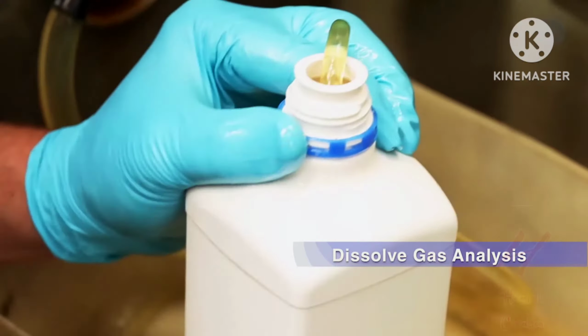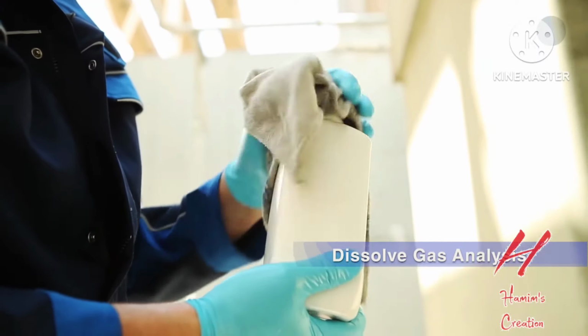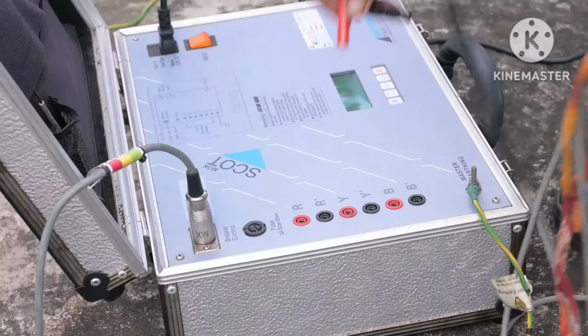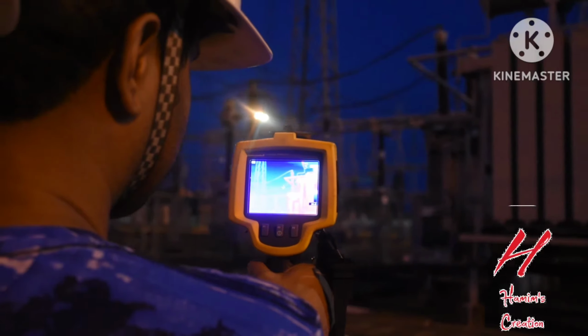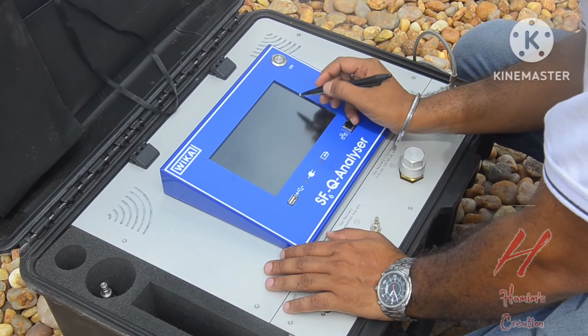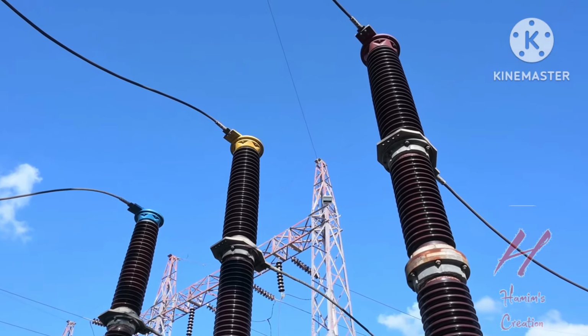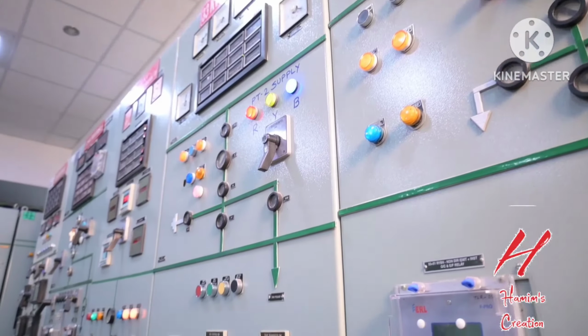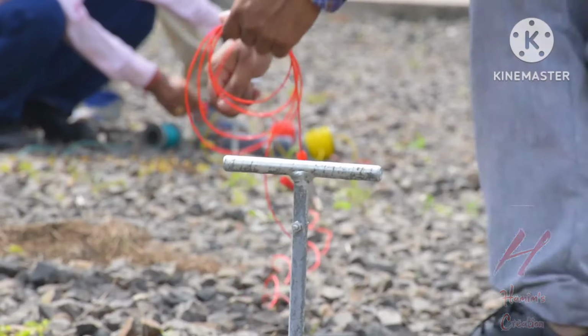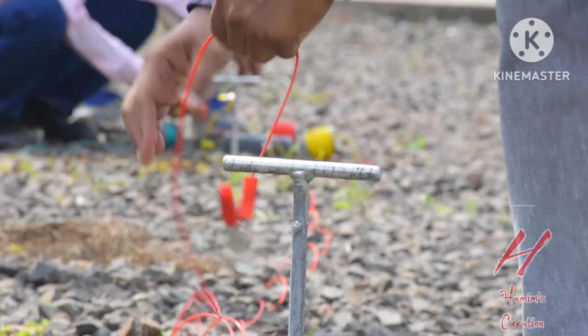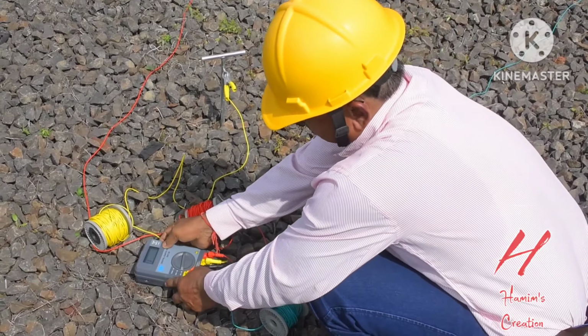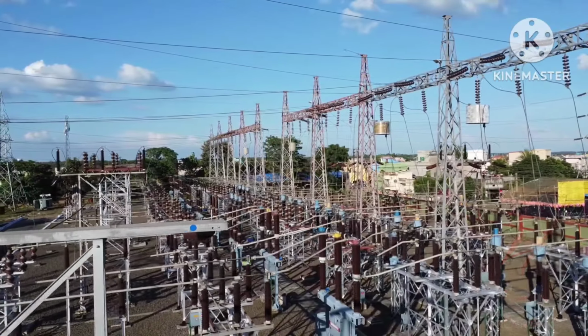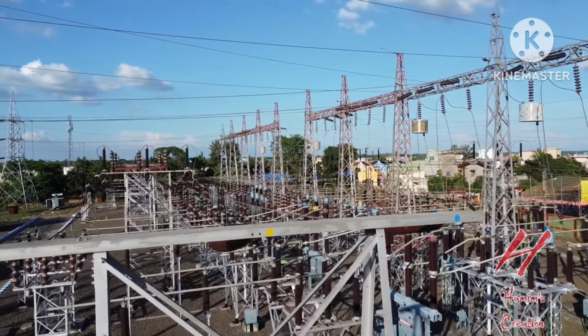dissolved gas analysis test of transformer oil, contact resistance measurement, breaker timer of circuit breaker, thermovision scanning of clamp connectors, dew point measurement of SF6 gas of circuit breaker and periodical testing of relays, earthing resistance test by Megger make Earth Resistance Tester. With these activities, failure rate is reduced to great extent.